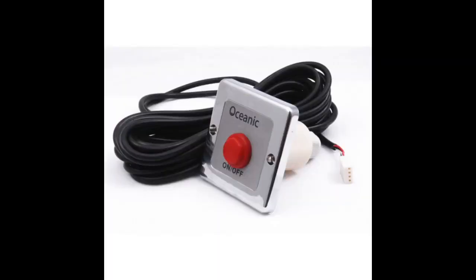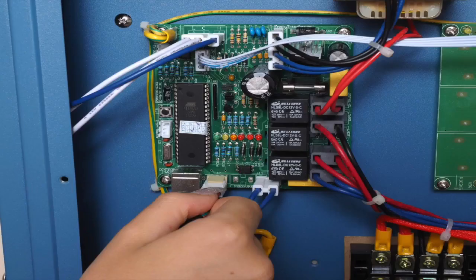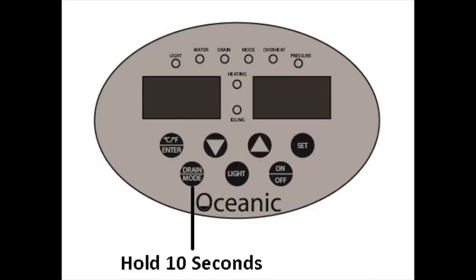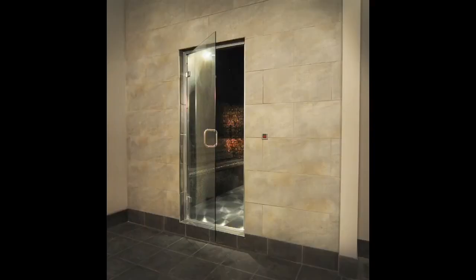Steam on demand. For commercial operators use our steam on demand mode to save on electricity bills. Install the keypad in the plant room and set the temperature. Hold the drain button for 10 seconds and it will activate steam on demand mode. When the button is pushed it will illuminate and the steam generator will steam for 30 minutes.